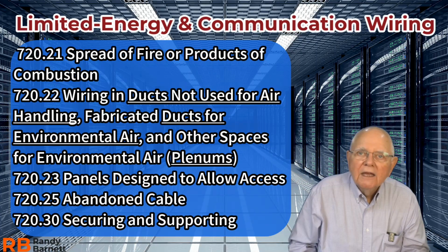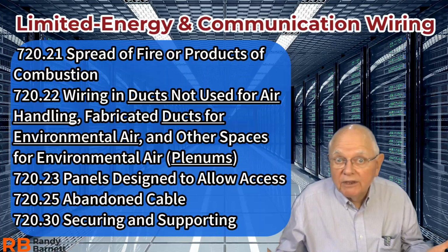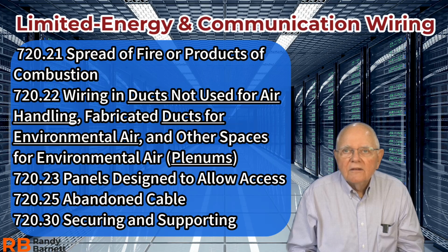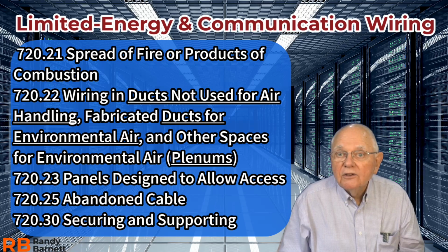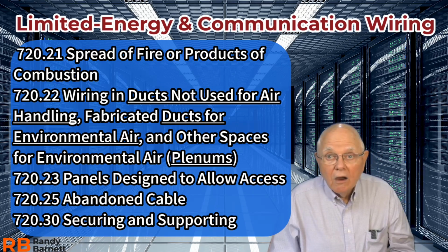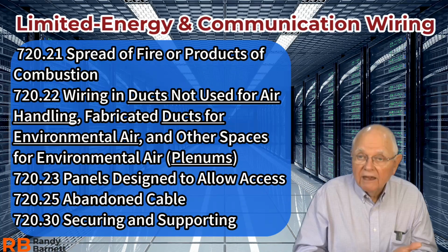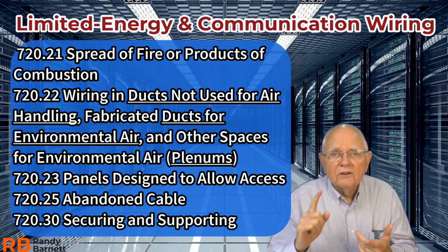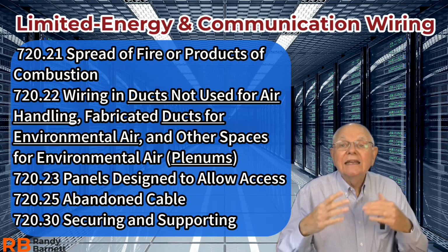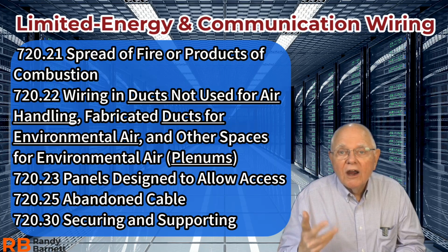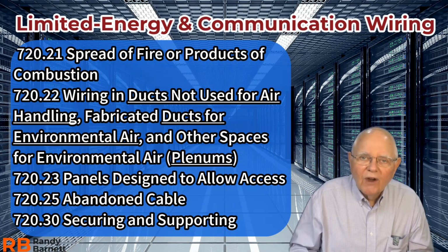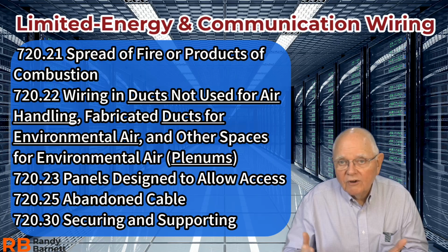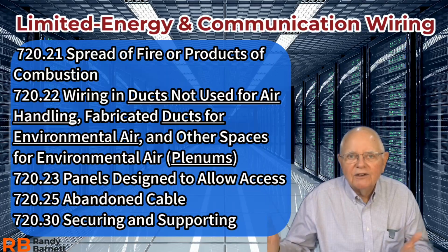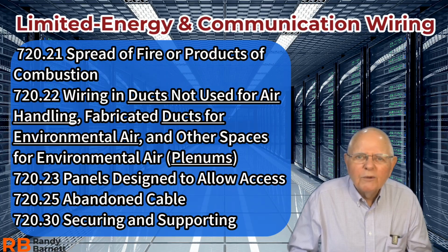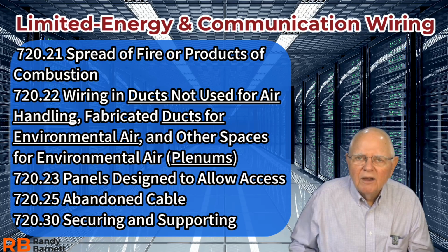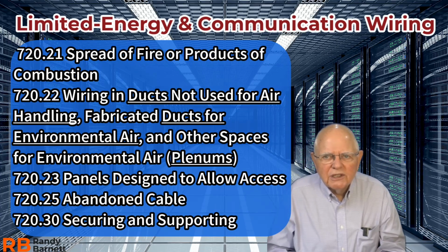Now, I can put listed cable where it says it's plenum rated. I can put those within that other space, within that plenum. I can use maybe some listed prefabricated assemblies, or I can run it in some conduits. And it even lists things like EMT and rigid and intermediate metal conduit, flexible metal conduit. And I can even use surface mounted raceways, or I can install a metal raceway if there's no access available for people, right? So if there's no access to the surface mounted raceway, I can go ahead and install that. But generally, what are we going to do? We're probably going to use some listed cable up there above that suspended ceiling, maybe run it in some EMT, whatever it is we're doing, okay?